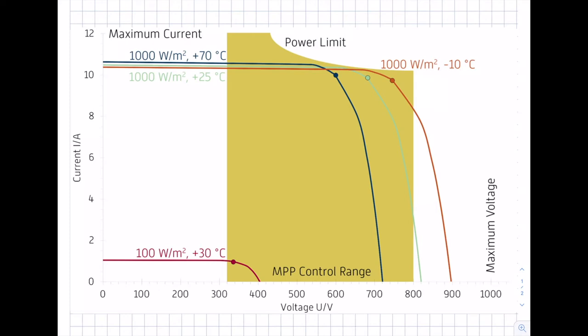Next, there is an MPP control range. The inverter is only able within this MPP voltage range to identify the maximum power point on the IV curve of the PV generator. In this case, the range goes from 320 volts up to 800 volts. The MPP of the marked spots on the IV curve must be within this range for the inverter to track the maximum power point. The green curve represents the IV curve under standard testing conditions.